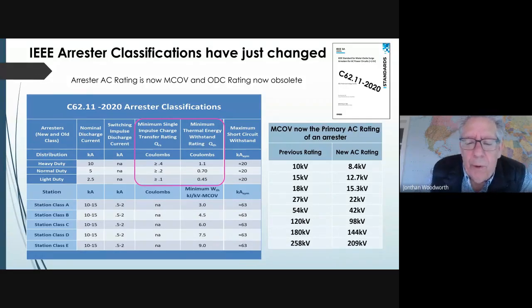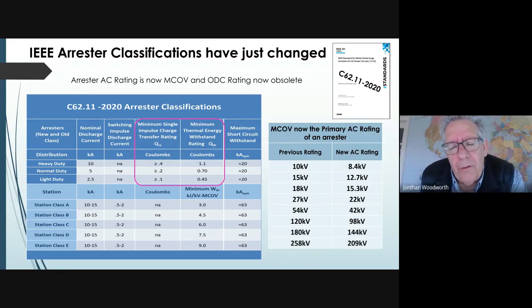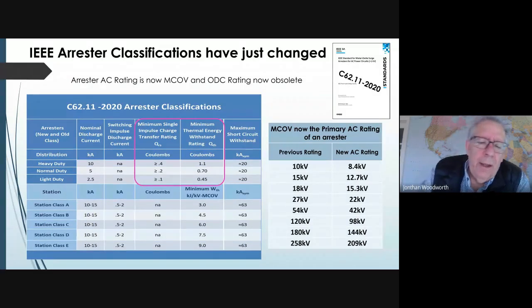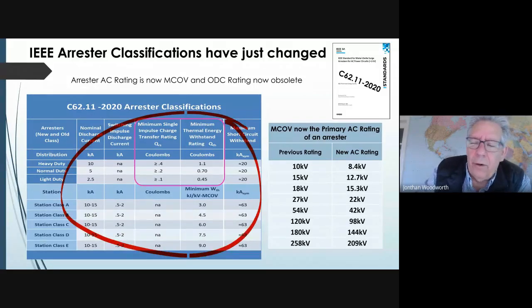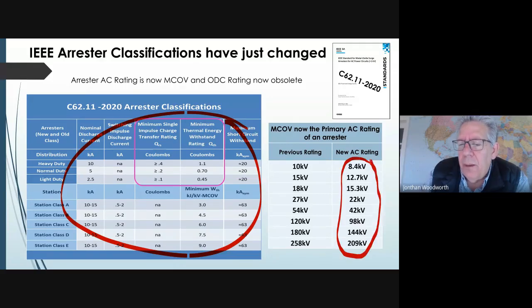Actually, the only country that really uses IEEE standards is the U.S. Most of the world tests and specifies arrestors per the IEC standard. And as of the last 10 years, these two standards have come together. So if you buy an IEC specified arrestor, it's going to really be specified the same way for IEEE. We all have tables that tell you what the currents are, what the ratings are. The Uc or the MCOV level is what an arrestor is usually rated by. We'll talk a little bit more about that in a second.